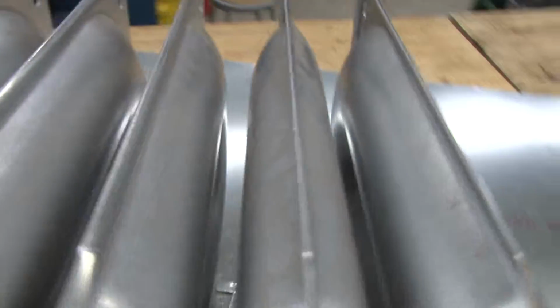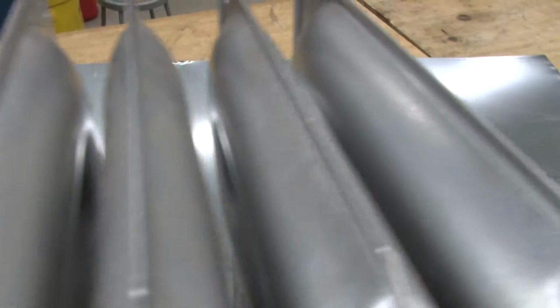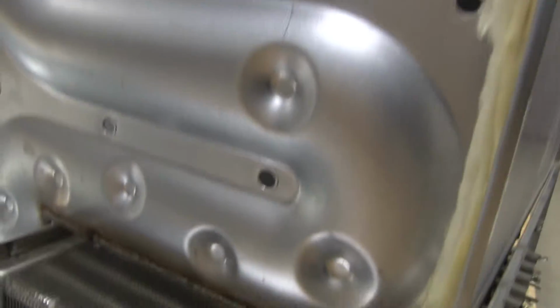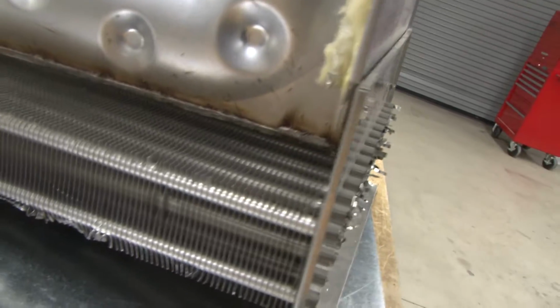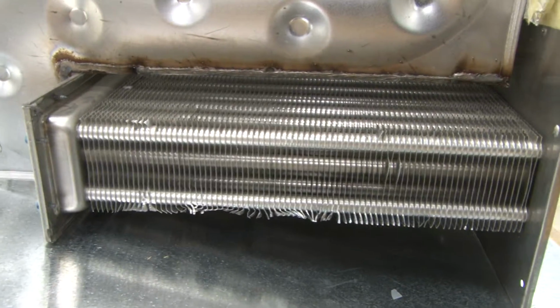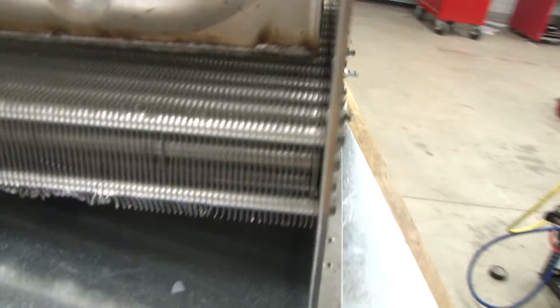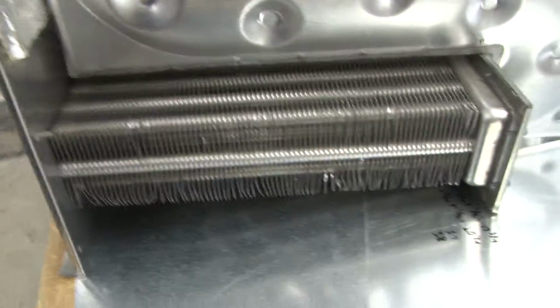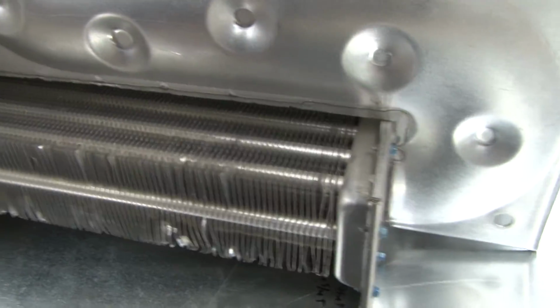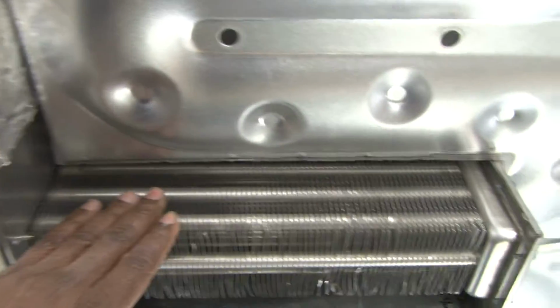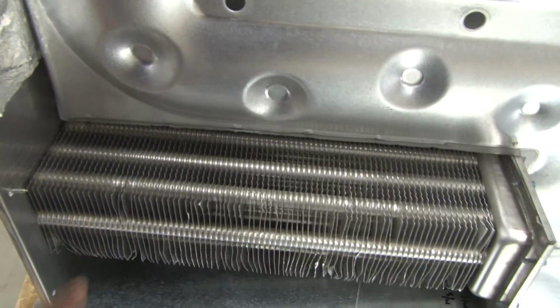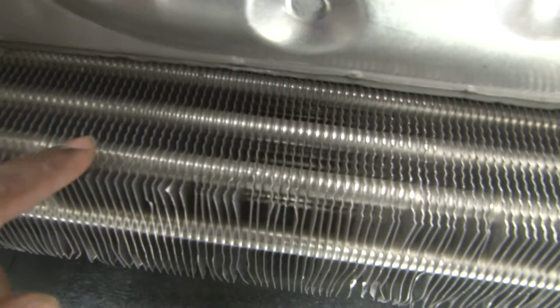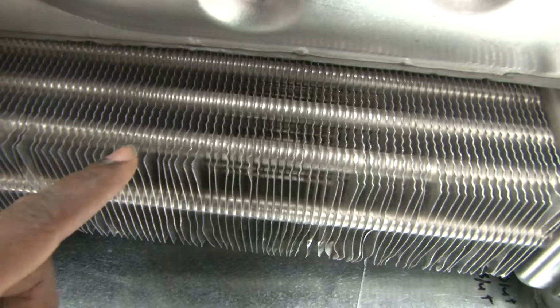As we look at how it is constructed, we can see that the ports are exactly the same. Each clamshell heat exchanger is exactly the same for each one, and each burner has its own section to be able to extract heat. But the secondary heat exchanger is designed to take the great bulk of heat energy and cause a latent heat change inside of these tubes. They put fins on it to help give it more surface area, so these fins will aid in pulling the heat out of these tubes.